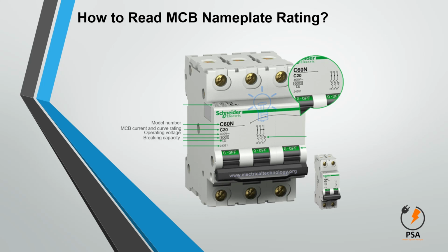4. MCB breaking capacity. Breaking capacity can be defined as the maximum level of fault current which can be safely cleared. It is written in numerals, like in the example, it is 6,000. It means 6,000 amperes, which equals 6K. Choose breaking capacity as per the fault level possible. Since it is a parameter which may increase or decrease the cost, it should be properly decided. Breaking capacity should be higher than the possible fault level. For domestic applications, where the fault level cannot be calculated easily, it is advisable to go for a standard breaking capacity of 10K, which is easily available.